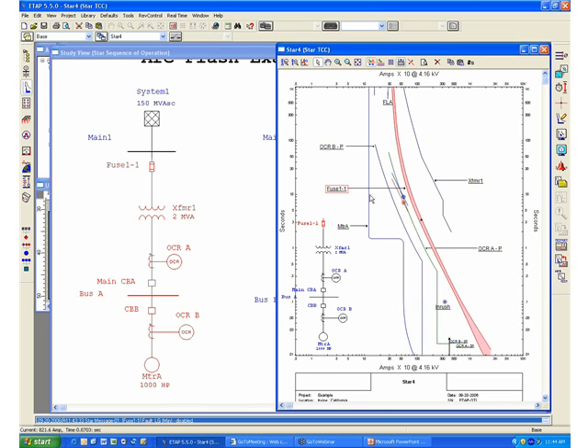To run an ArcFlash calculation in ETAP, you do not have to generate all the TCC curves. The program automatically accesses the library and the current settings for each protective device, and it will determine the full clearing time from all those devices.